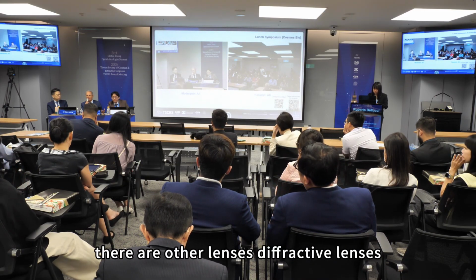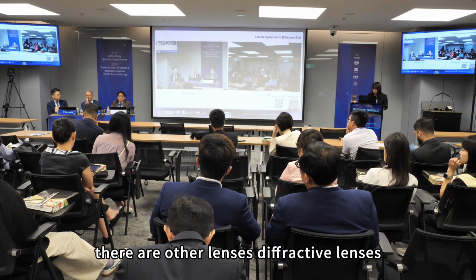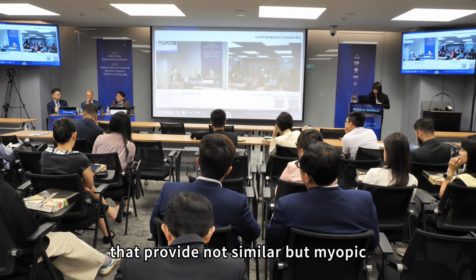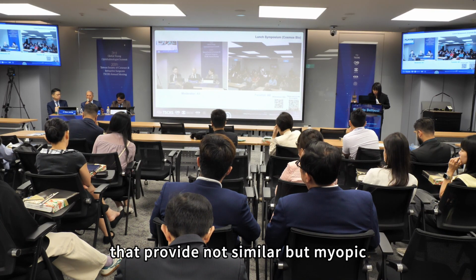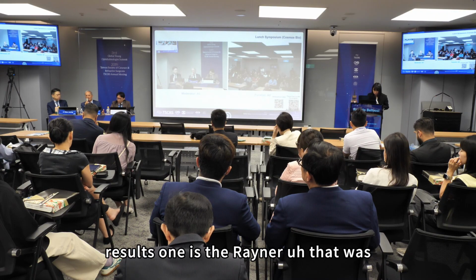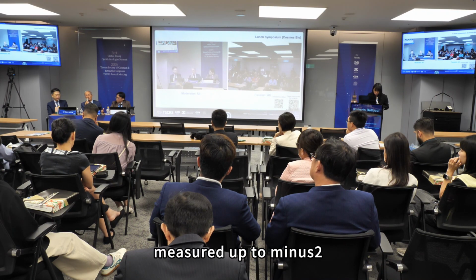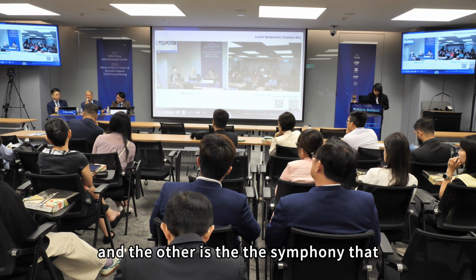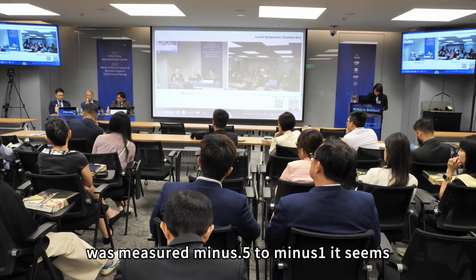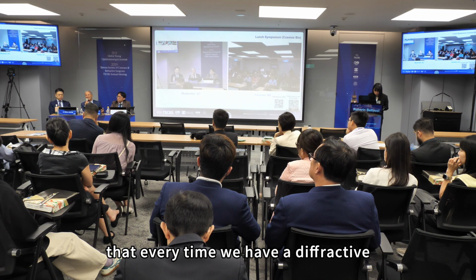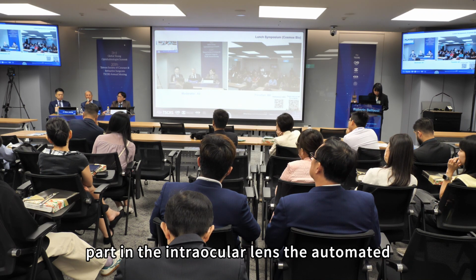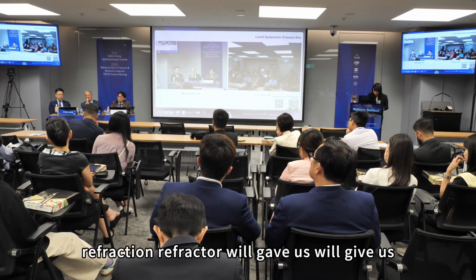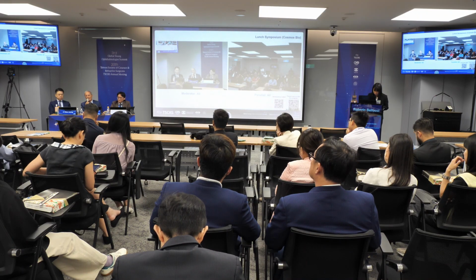There are other diffractive lenses that provide similar myopic results. One is the Rainer, that was measured up to minus 2. And the other is the Symphony, that was measured minus 0.5 to minus 1. It seems that every time we have a diffractive part in the intraocular lens, the automated refractor will give us myopia.